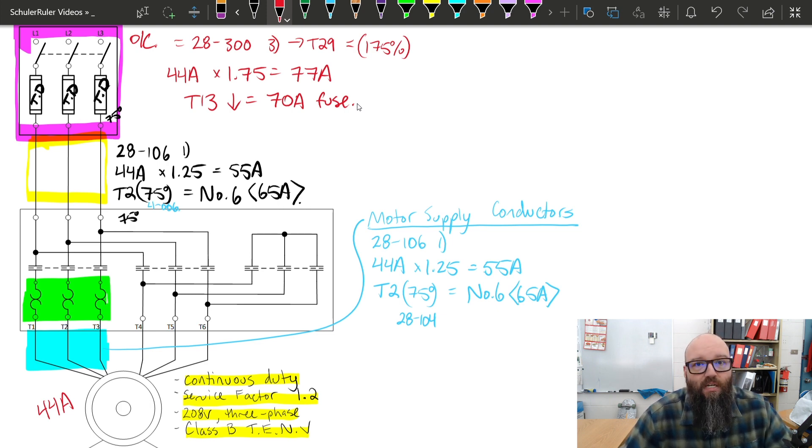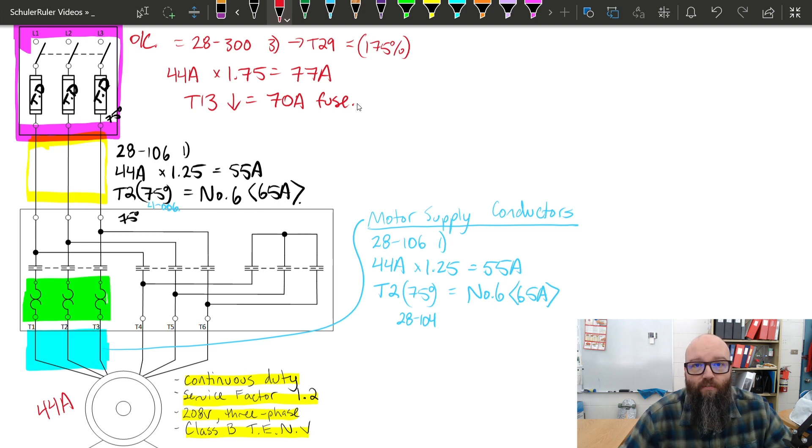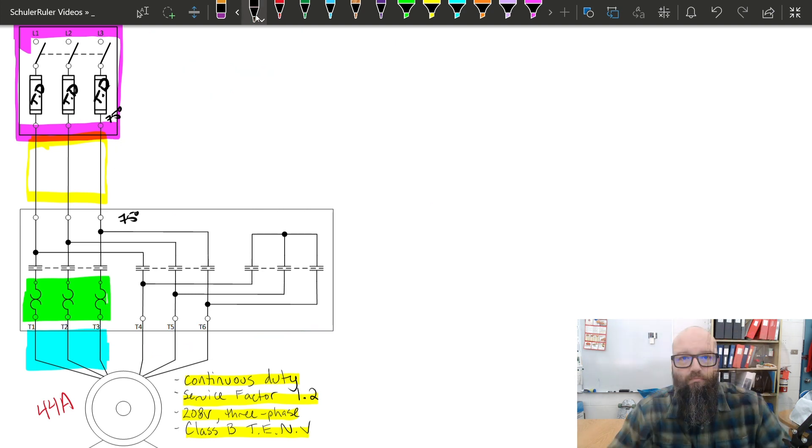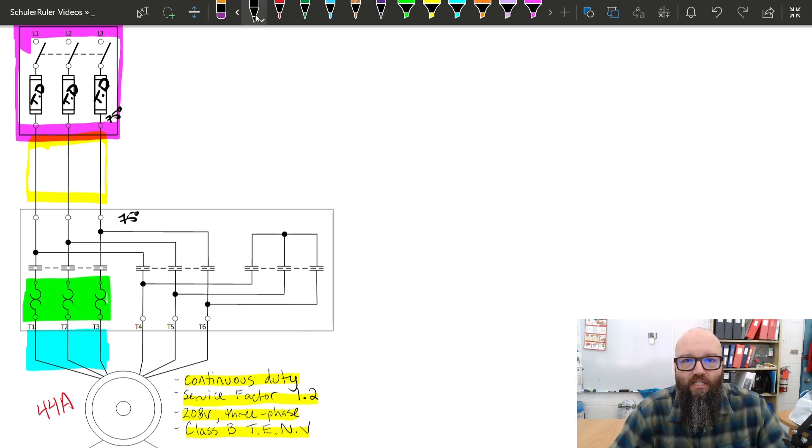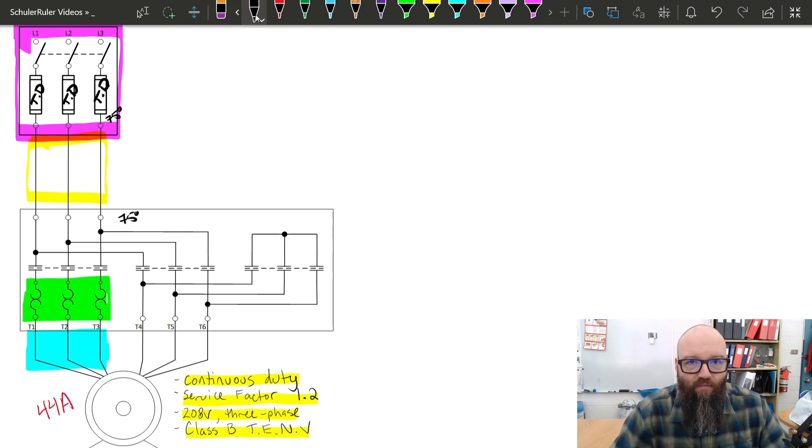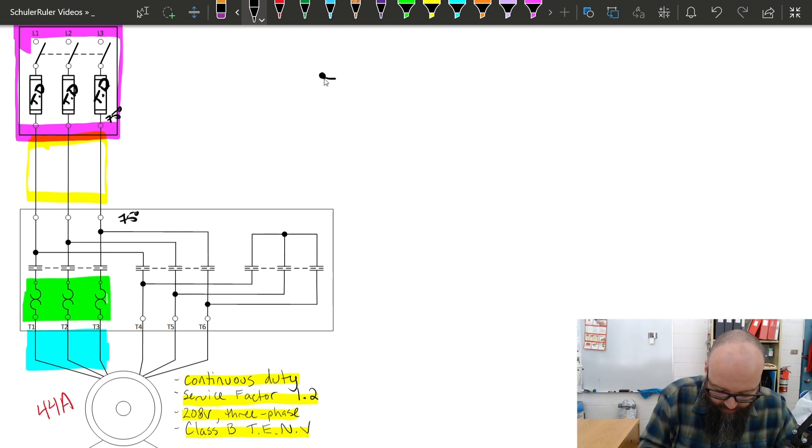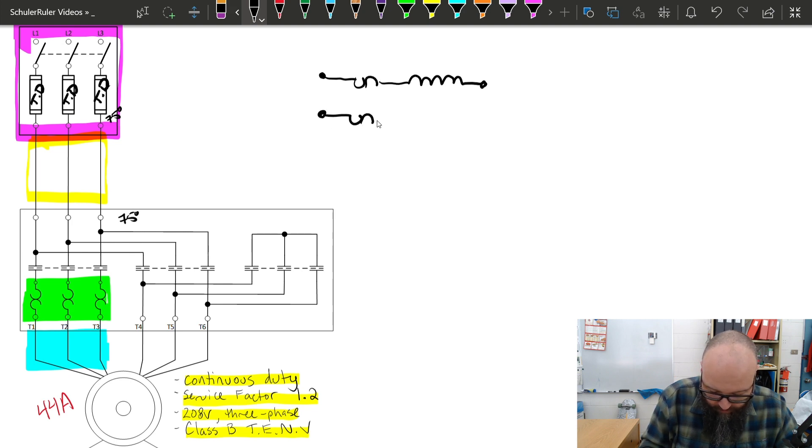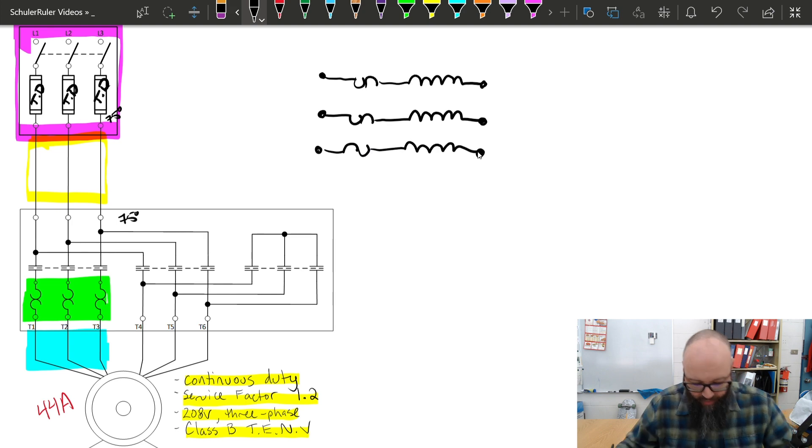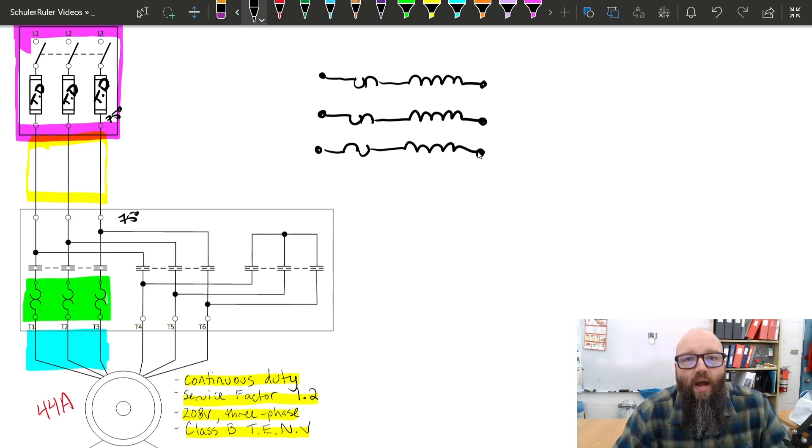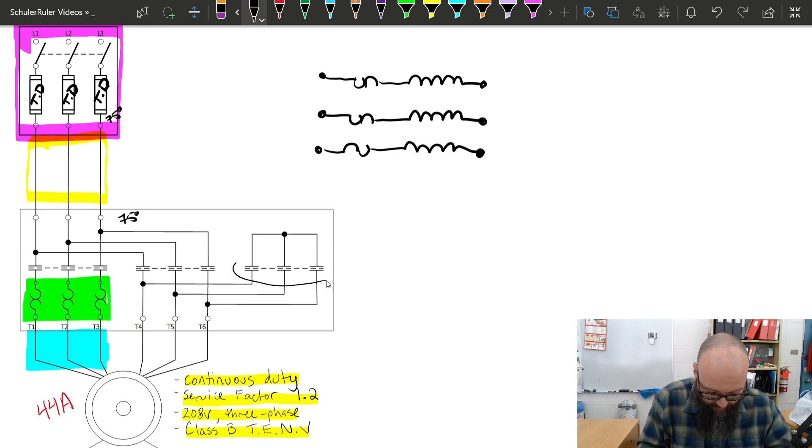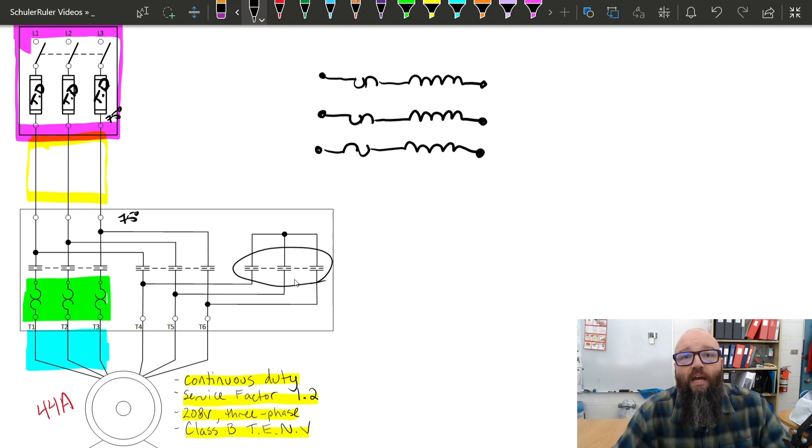Now, the change comes in specifically when we're dealing with these Y-delta start overloads. So what we want to focus on is the configuration of where those overload heaters are located with respect to the windings of our motor. Generally, what we're looking at is something like this. We have our overload heaters in series with the stator windings of our motor. And one of the things that we have to keep in mind with a Y-delta start motor is it starts in a Y configuration. Basically, we're utilizing this Y configuration so that it starts in a Y configuration with a lower starting current.